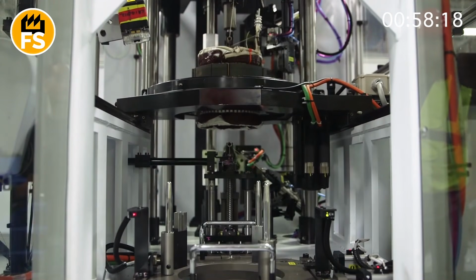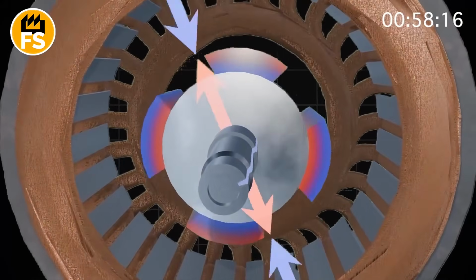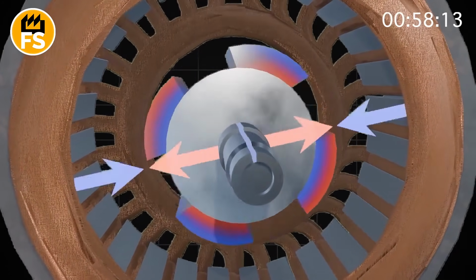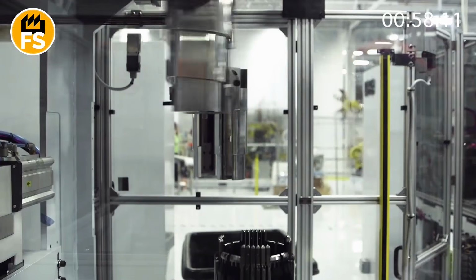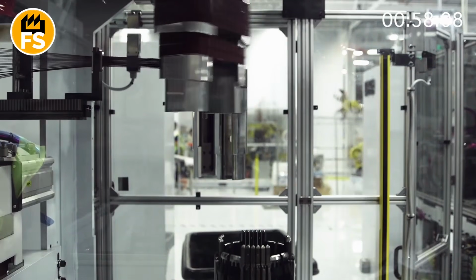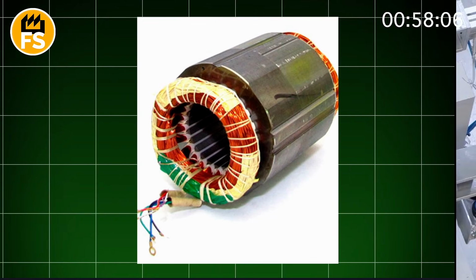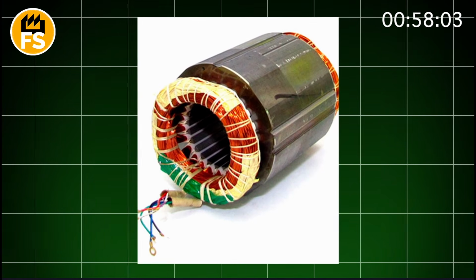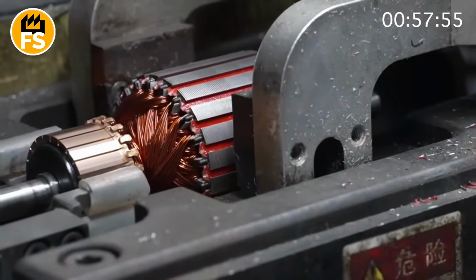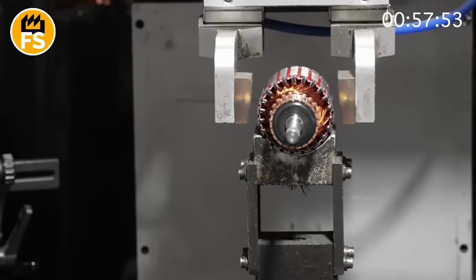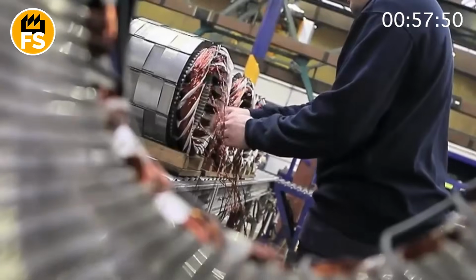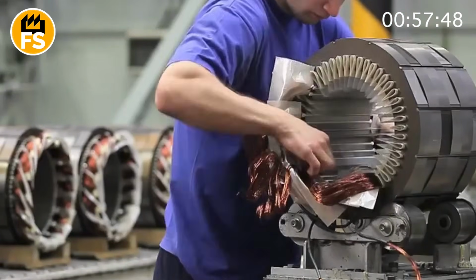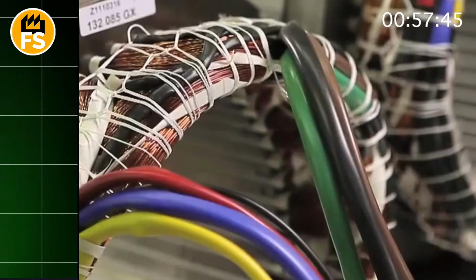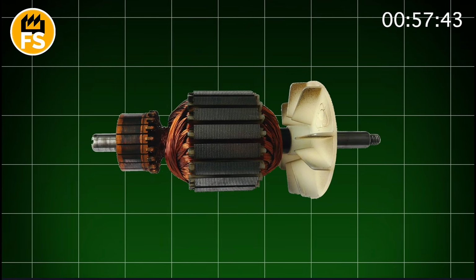Inside every electric motor is a true mechanical electrical universe. The main components of a motor are the stator, rotor, shaft, bearings, housing, as well as a cooling system and terminal box. The stator is the stationary part, located in a circle inside the housing. It's what creates the magnetic field that makes the rotor spin. Inside the stator is a core made of layers of thin electrical steel, which reduces losses from eddy currents. In the slots of the core is a winding of copper wire, connected in a special way to create a rotating magnetic field.